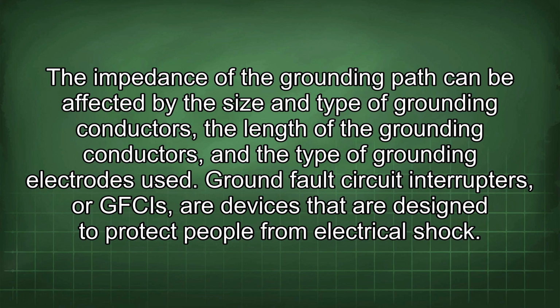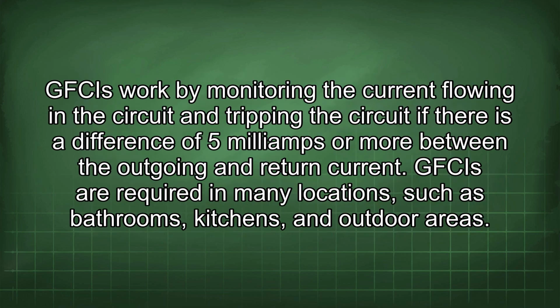Ground fault circuit interrupters, or GFCIs, are devices that are designed to protect people from electrical shock. GFCIs work by monitoring the current flowing in the circuit and tripping the circuit if there is a difference of 5 mA or more between the outgoing and return current. GFCIs are required in many locations, such as bathrooms, kitchens, and outdoor areas.